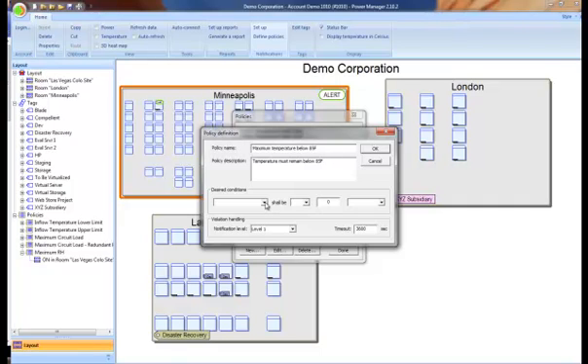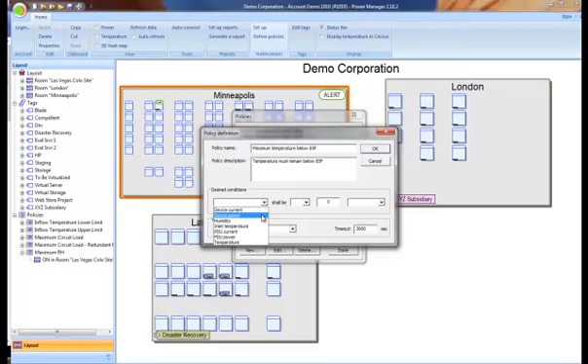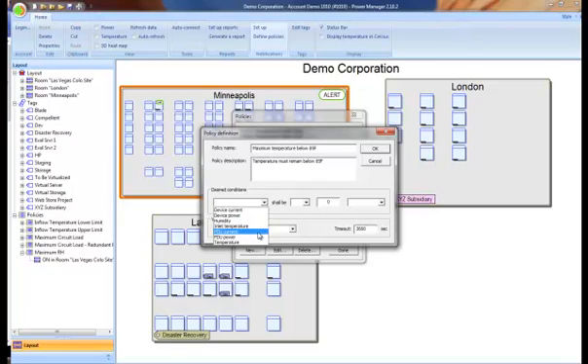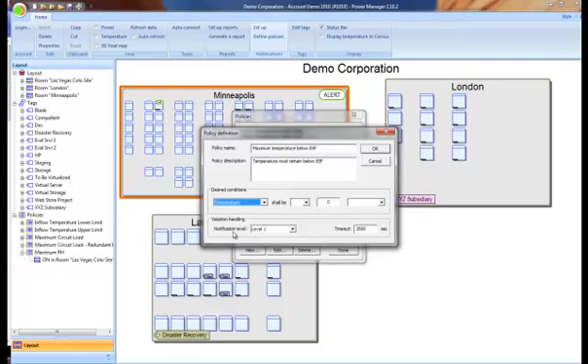Then we'll define how we want the policy to be put in place. You can set policies on a number of different attributes: on current and power at the device level, on relative humidity and inlet temperature if you're using our environmental monitor product, and on power and current at the PDU level as well as temperature as read by the Packet Power smart power cables. That's the criteria we're going to select.